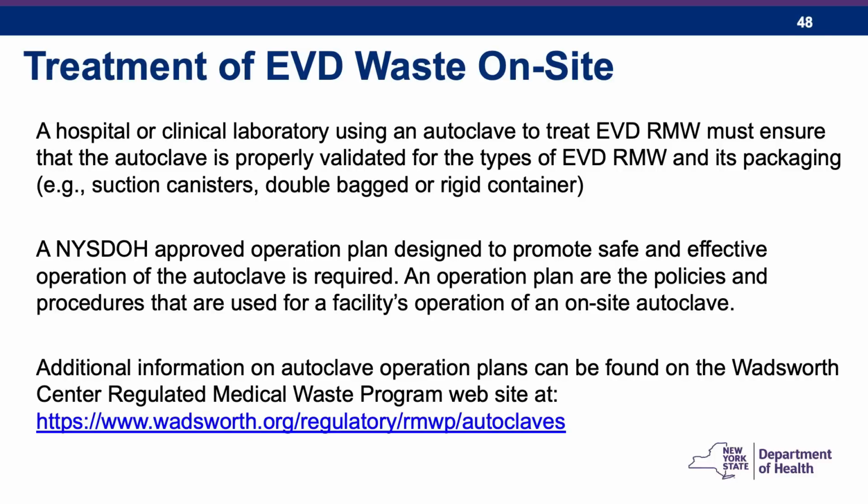We have additional details that will be available on our Ebola medical waste guidance that will be posted on our New York State Department of Health Ebola website, so you can look for details there. So if a facility operates an autoclave using operating parameters other than those that are described within our regulations, that changed procedure must be approved by the New York State Department of Health, and it becomes an alternative treatment technology. So I just want to emphasize that any changes in normal operating procedures of an autoclave need to be approved as an alternative system by the Department of Health. And again, we have additional details at the link below.